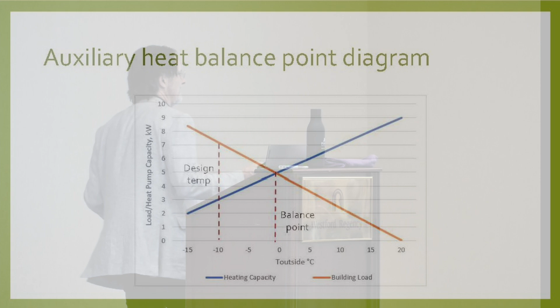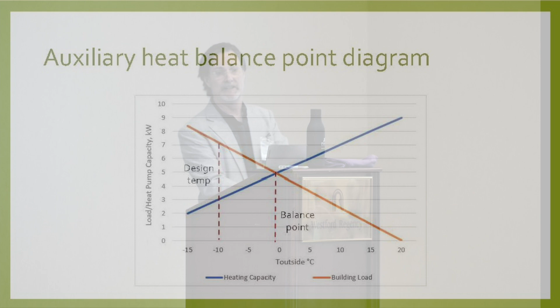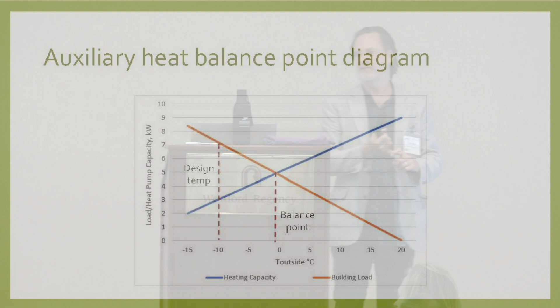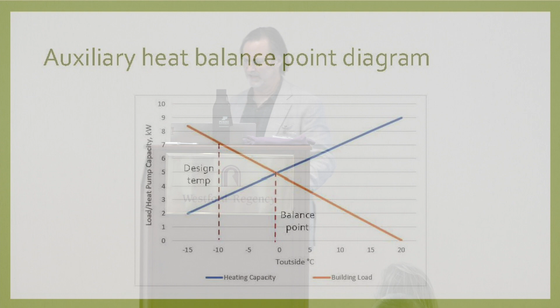All heat pumps produce less heat when it gets colder outside. They also produce less cooling when it gets hotter outside, right? The bigger the temperature lift, the harder it has to work, uses more electricity, has less capacity. There's always a drop-off, no matter what kind of heat pump it is, no matter how good it is. But a conventional one has a very steep drop-off like this.